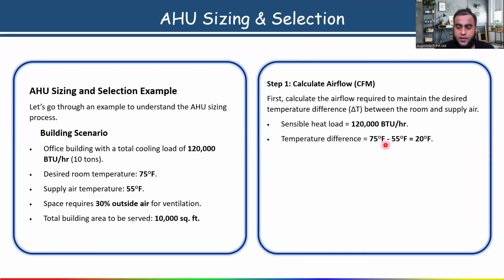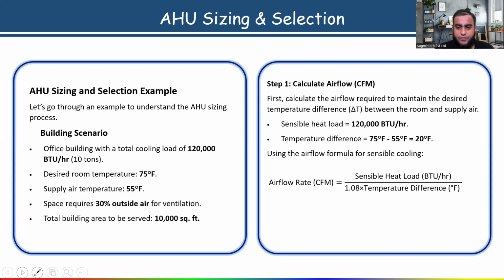Suppose the desired room temperature we have to maintain inside the room is 75, and the supply temperature is 55, so near about 20 degrees Fahrenheit. Now use the formula to calculate the airflow CFM. What is the formula? Sensible heat load in BTU per hour divided by 1.08 into temperature difference in degrees Fahrenheit. Is it clear, all of you? Let me know, please. Am I right? The formula is correct.